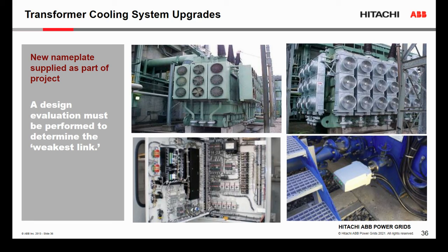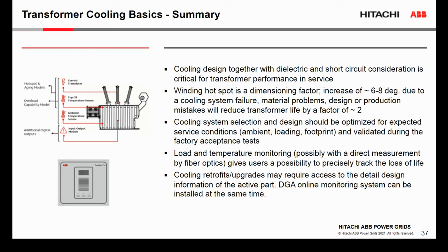So every cooling upgrade, especially when we talk about a change in the rated MVA, requires design evaluation, and we have to consider not only new coolers, but we have to look at the bushings, the tap changer and internal connections. We have to recognize that some modifications have to be done to the control cabinet as well. And then as a summary, I just want to say that the cooling is really critical for the performance of the transformer. When we increase the hotspot temperature of the windings, we can significantly reduce the life of the transformer.